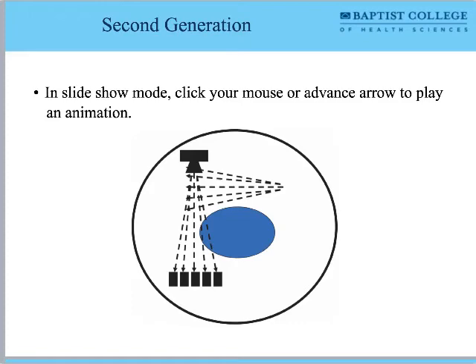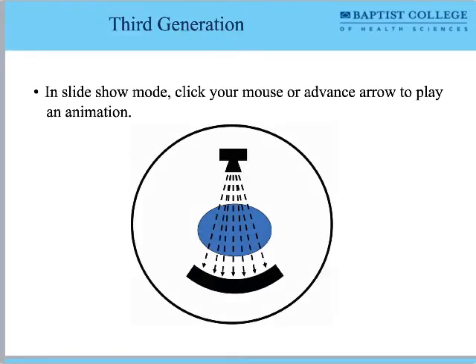The second generation improved by using a fan beam with multiple detectors, but still performed that translate-rotate scanning motion because they still lacked the power supply for continuous rotation. The third generation — which you will mostly work on — uses a fan beam of x-rays and a bank of detectors contoured to the inside of the gantry; the entire assembly spins continuously because we now have slip ring technology, with both the detector and the tube spinning at the same rate.